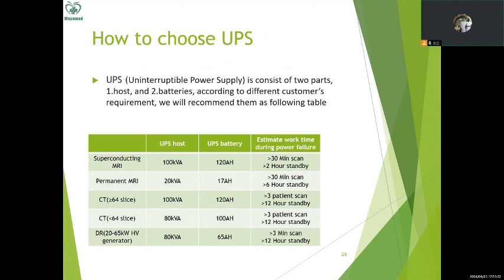For CT, which is more than 64 slices, the host of the UPS should be 100 kVA, and the UPS battery is approximately 120 Ah. If you use this configuration, the estimated work time during the power failure is more than 3 patient scans, which is quite enough for the power failure. And the standby of the system is more than 12 hours. For the CT system which is less than 64 slices, the UPS host can be 80 kVA and the UPS battery 100 Ah. Also support 3 patient scans and 12 hours standby.